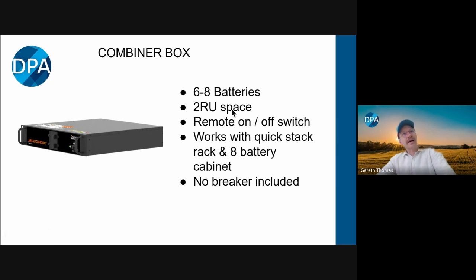It has like a rat's tail that comes out the back, so all the cable connections come connected to the bus bar that's inside there, and you just slot it into your racking, and then run the cables through however you're doing it to the front of the batteries, which makes it a bit quicker and easier because you don't have to attach it to the bus bar.